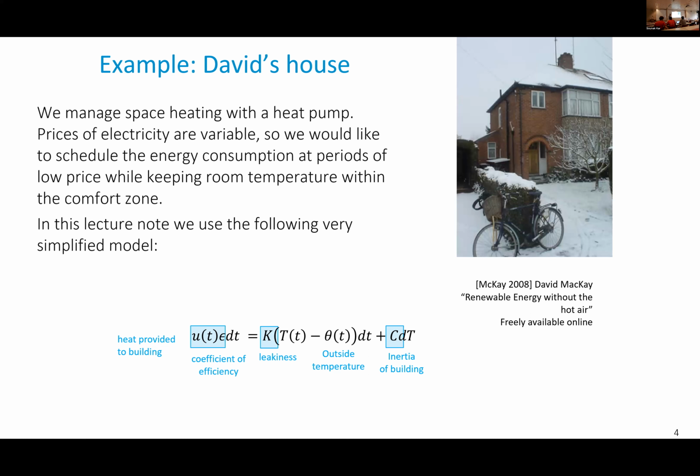It has a capability to store the heat in the walls, in the building, in everything, if the windows are not large open. So if your house is at a temperature of 21 degrees and you stop heating, then the temperature will be perhaps 20 degrees 1 hour after, without heating at all. That means during 1 hour, you were relying on the heat that is stored in the building itself. Of course, it's not a storage like pump storage, that you will be able to use over long periods of time, like days or weeks, but it has some inertia that we would like to capitalize.